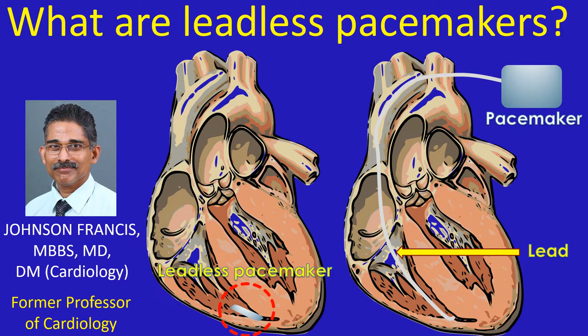The weakest link in the pacemaker system is considered to be its lead, sometimes called its Achilles heel. This is because the lead system is prone to infection, fracture, failure, and dislodgement. The more the number of leads, the more the complications, as in sophisticated systems like dual chamber pacemakers and biventricular pacing devices. The incidence is compounded over time with longevity of the device and the recipient.